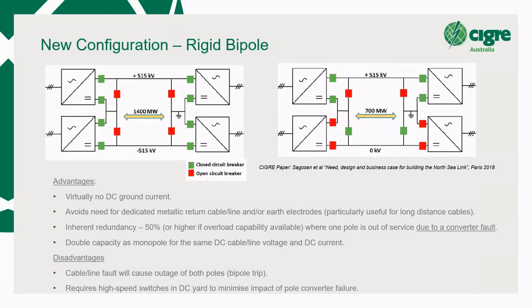Now, the last one is this new configuration that everyone's talking about, which is a rigid bipole. Now, a rigid bipole, one hasn't been commissioned yet, but there are three under construction right now in Europe: NSL, Nordlink, and Viking. And most of these projects are actually very long cables, circa 700 kilometers. So what a rigid bipole effectively is, is a bipole without either an earth electrode or a metallic return.